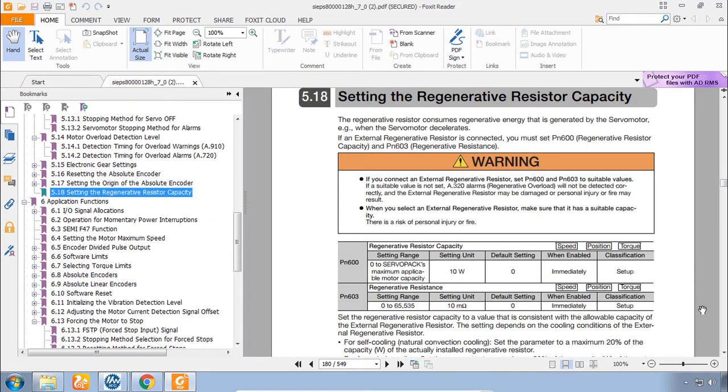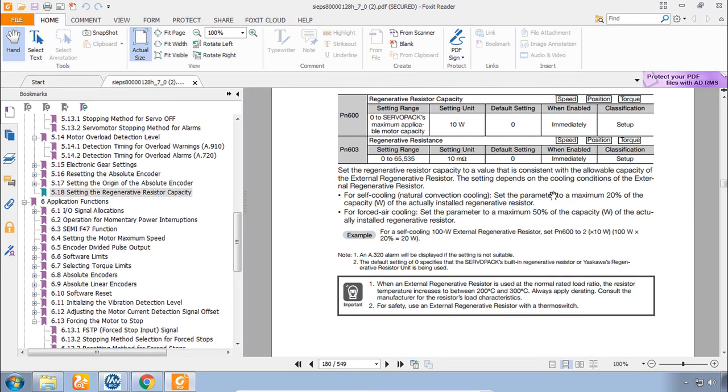And in the manual that is section 5.18, Regenerative Resistor Capacity. You see that PN600 is the wattage of, not the resistor necessarily, but of the capacity of the resistor. If you read through here you'll see that there's a 20% derating that we require for safety. And new for Sigma 7 is the parameter PN603, the resistance of that resistor in ohms. If you do have connected a regen resistor you need to consider these parameters in order to protect both the resistor and the amplifier.